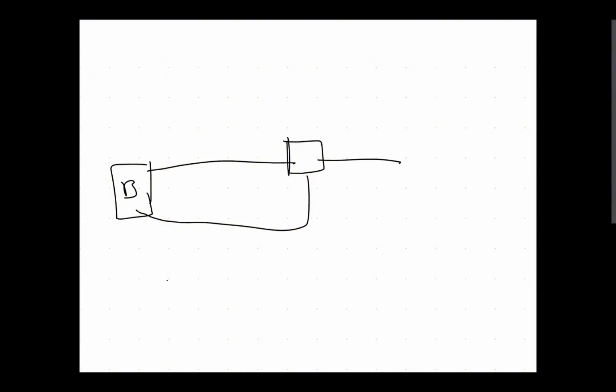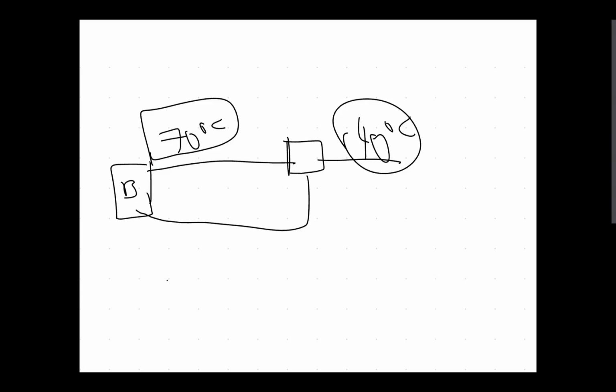And just to point out the three-way part of that last picture, similar drawing. We have supply side and then a return to the boiler. Generally, the boiler will have its own set point and its own temperature it'll maintain. This is tied to a physical safety. It's usually a limit controller and a high limit controller. For this one, it was set to approximately 70 degrees, and the sensor that we want to supply to the building was looking for 40 degrees. But that's usually how these are separated, and those are two important numbers to know.